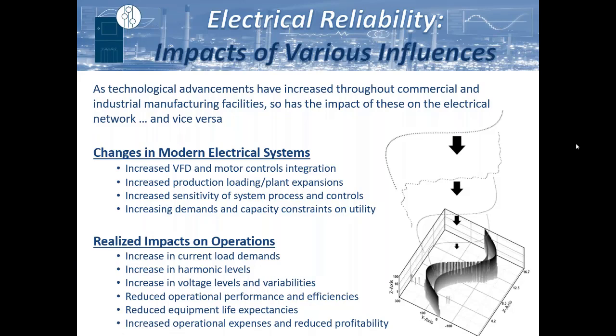So obviously, over the past 30, 40 years, with the advancements of various different types of technologies and the integration of those into not only industrial applications, but residential and commercial buildings, with the advent of VFDs and motor controls and the sensitivity of PLCs, and sensitivity of equipment throughout, the impact as these are integrated onto the network is a cumulative effect. So what happens in one facility has an impact on the neighboring facilities and, as such, on the utility grid as well. As we've incorporated more controls and more features and functionality, this has an impact on the electrical network, inducing additional harmonics, which induces heat, and ever-expanding production increases, so maximizing capacity and running into capacity constraints.